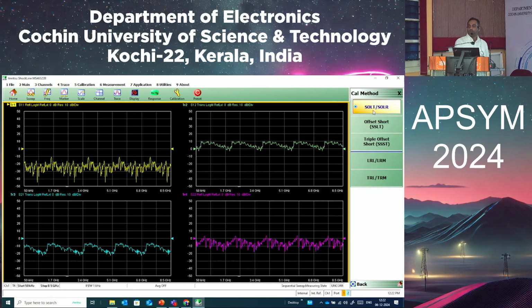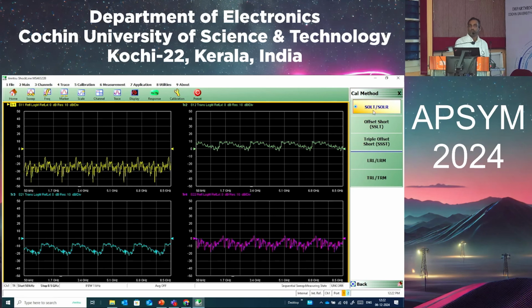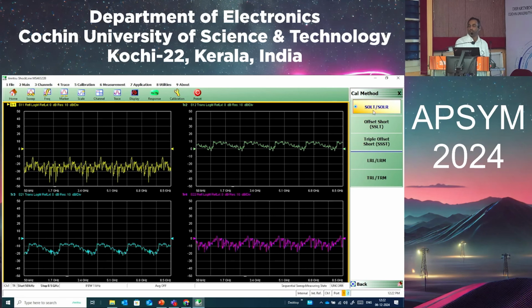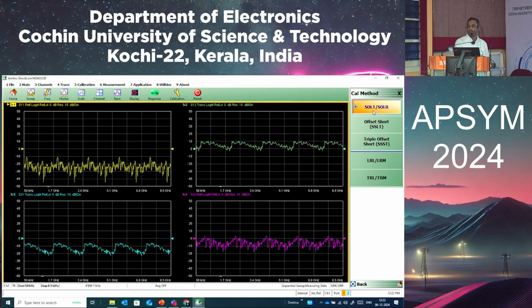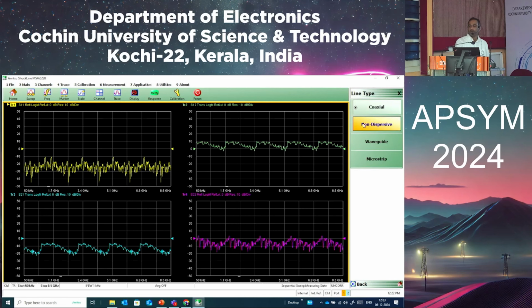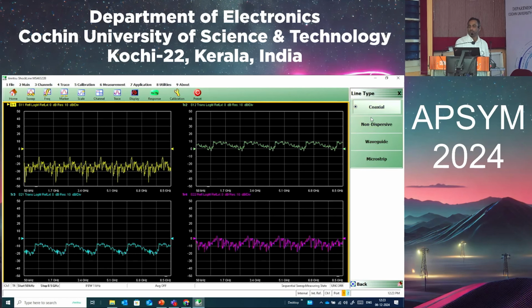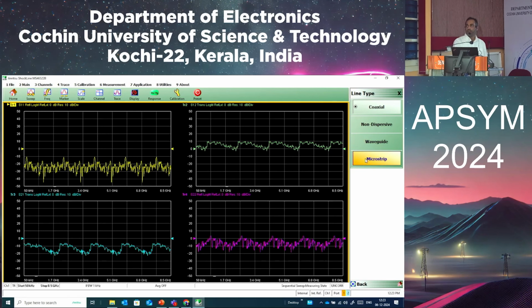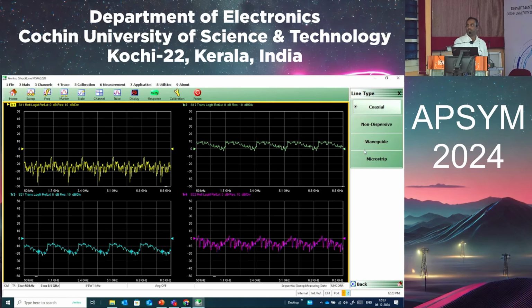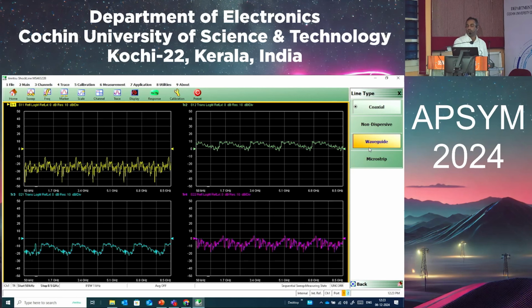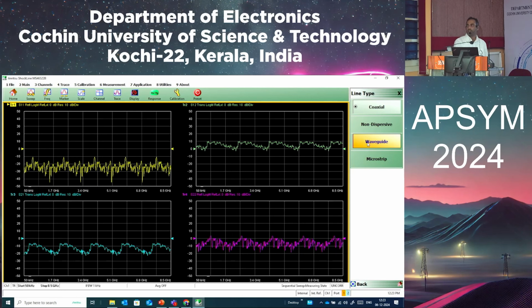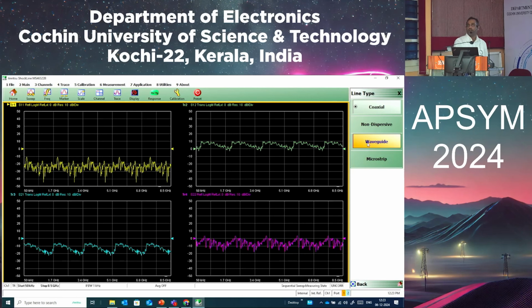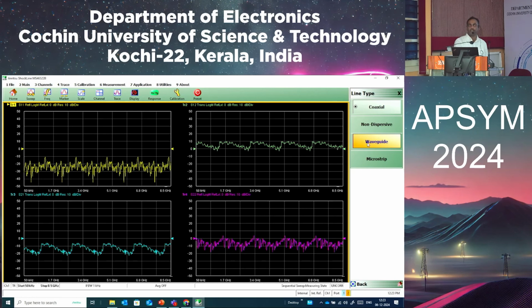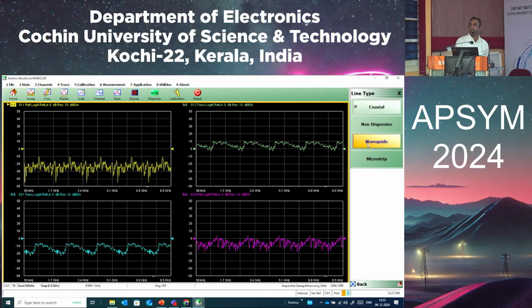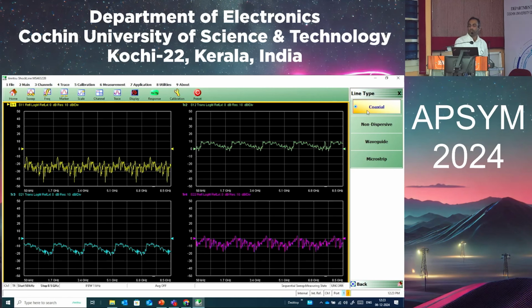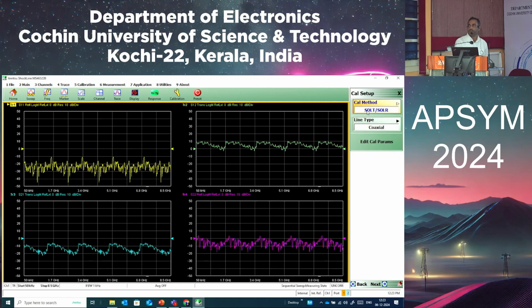Okay, so now, most of the time for a 50 ohm or coaxial setup, we will be doing the SOLT calibration. And this is the type we have to select, whether you are doing it for a coaxial, a non-dispersive waveguide, or a microstrip. We have to select which is the DUT. Suppose you have a waveguide, you have to select waveguide and do the double SSLT calibration or triple SSST calibration. For coaxial, we will do the SOLT calibration.